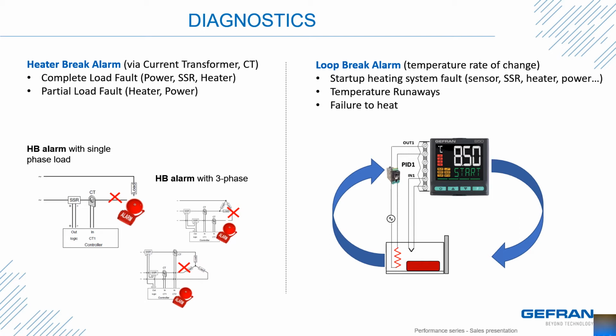A good application for this could be a packaging machine, where a heated bar for sealing bars tend to be in constant motion. When the heater stops pulling current, you know the temperature will begin to fall, but when does it stop sealing properly? With the heater break, we can see the loss of the power, turn on the alarm, maybe stop the machine and get the heater replaced and running and sealing properly.